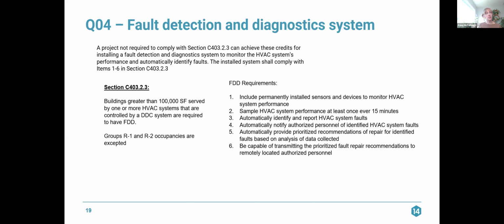So we always had fault detection, and well, not always. Starting in 2021, we had fault detection and diagnostics listed in the code for systems serving an area 100,000 square feet or larger. Now, under the 2024 IECC, if you are a building 100,000 square feet or larger, served by one or more HVAC systems that are controlled by a DDC system, you're required to have fault detection and diagnostics. Groups R1 and R2 occupancies are excepted.